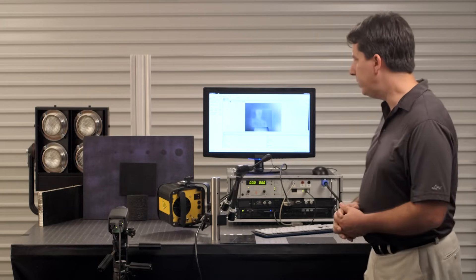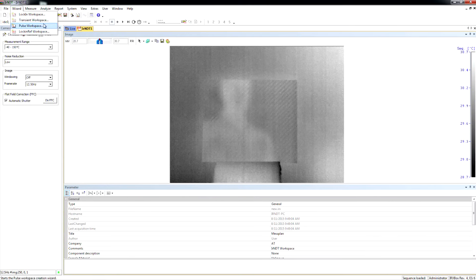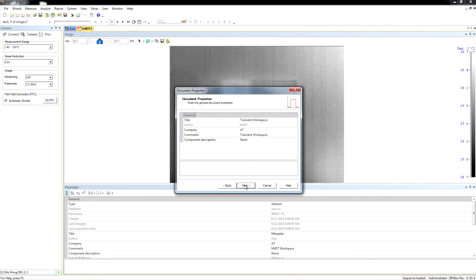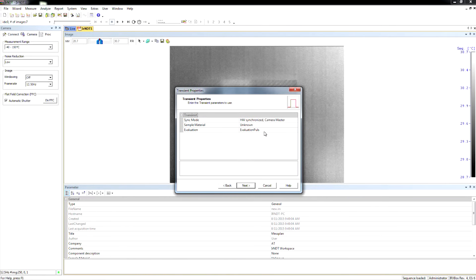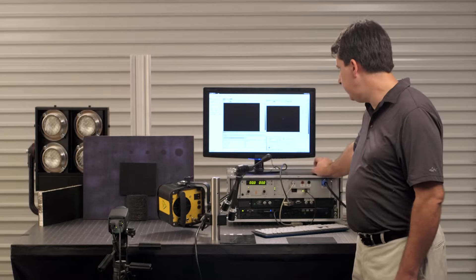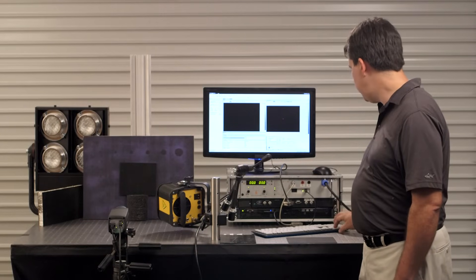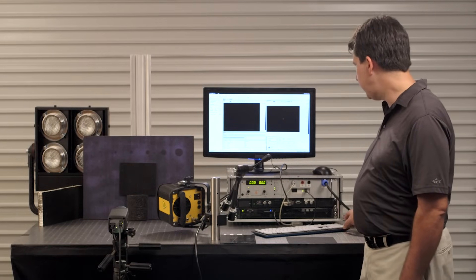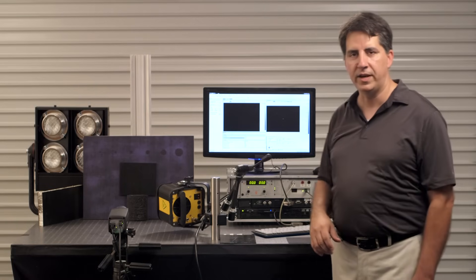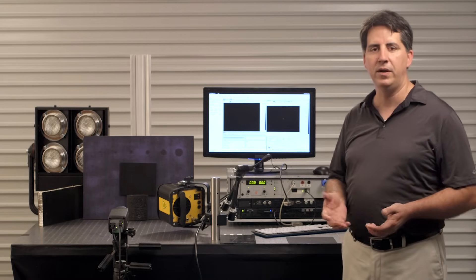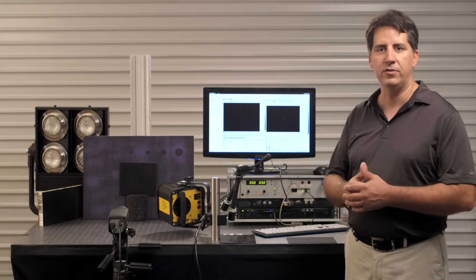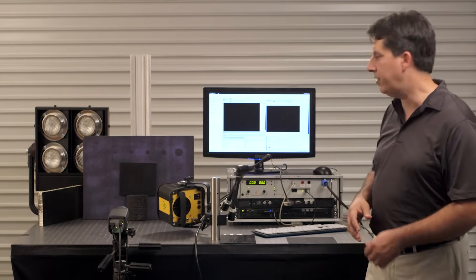So we're going to set up the wizard for our workspace, and it requires very little in the way of parameters. You simply need to tell it what type of excitation source you need, which is a halogen lamp for us, how you want the camera to run, and we want it to run in free run. And then the last bit of information is how long you want to measure for. We're going to say 30 seconds, so that's going to be 30 seconds total. 10 of those seconds are going to be with the lamp on. 10 of those seconds are going to be watching the part cool down after the lamp turns off.